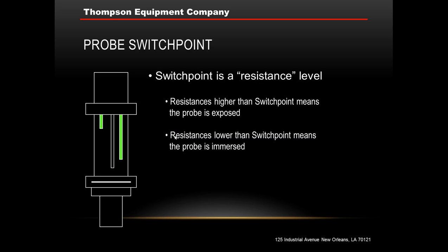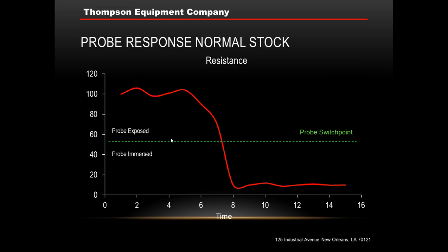The switch point is a resistance level. Resistances that are higher than the switch point are going to be interpreted by the system to mean that the probe is exposed — just hanging out there in air. Resistances which are lower than the switch point will mean that the probe is immersed in filtrate. Graphically, the probe switch point is the dashed line. Resistance values which are higher are interpreted to mean the probe is exposed, and lower values mean the probe is immersed.